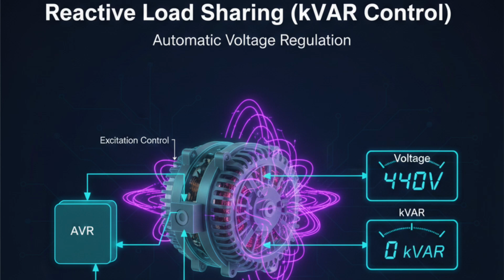Reactive load sharing, kVAR control. Reactive load sharing controls kVAR. This is controlled by the automatic voltage regulator, or AVR. If one generator has higher voltage, it will supply more reactive power. If voltage is lower, it will absorb reactive power. AVR adjusts excitation current to balance reactive load. Improper reactive load sharing can cause voltage instability, generator overheating, unequal power factor, protective relay trips. Proper AVR tuning ensures stable voltage and balanced kVAR sharing. Remember, voltage controls reactive power.